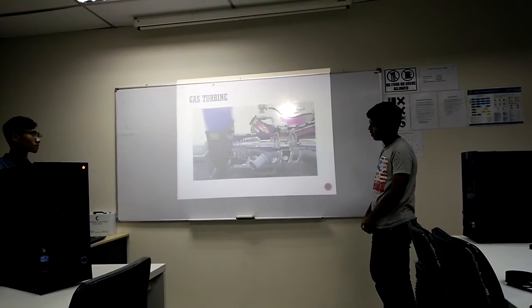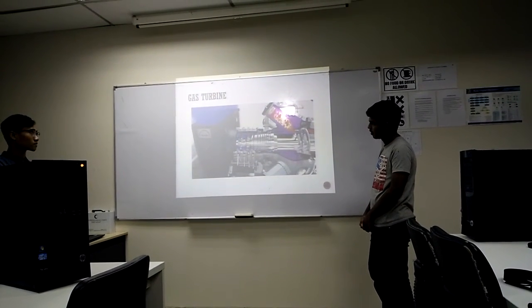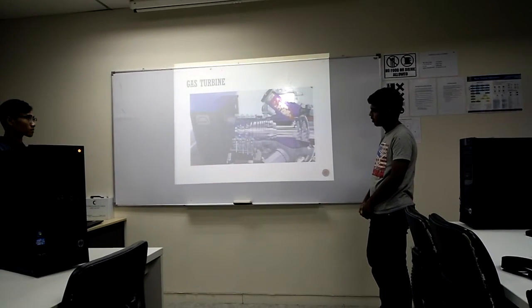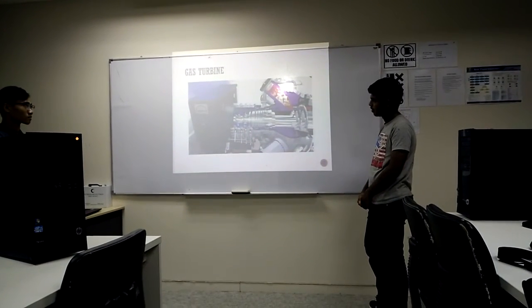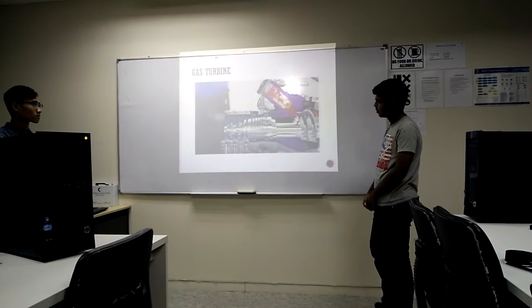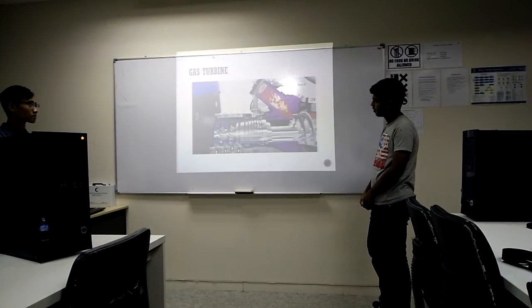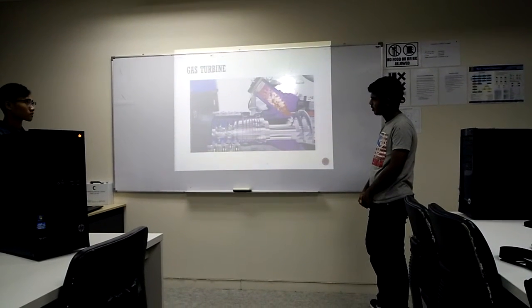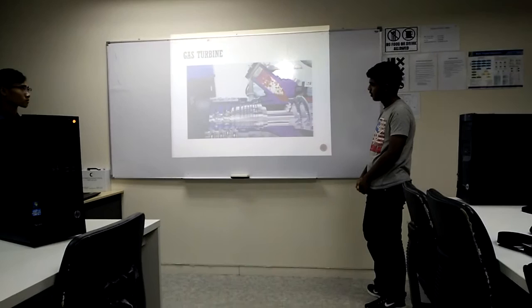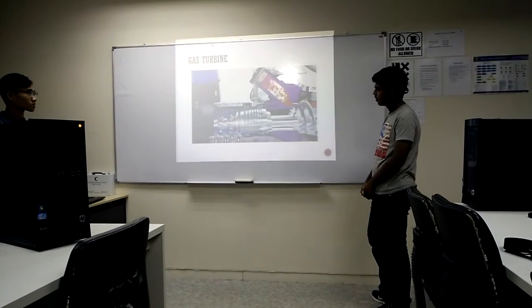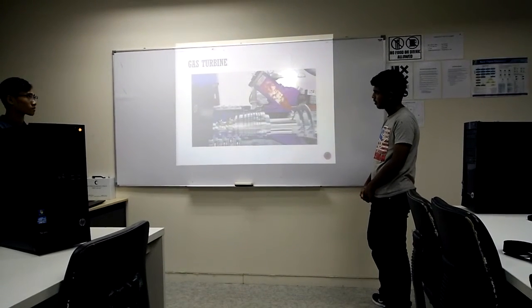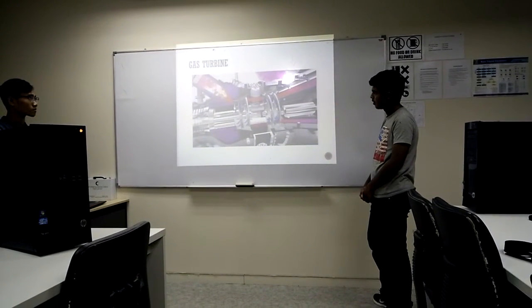Let's take a closer look at this process. Due to the spinning motion, the blades of the axial compressor strike the air. They conduct it into the turbine while compressing it in the process. A flow is created that passes through the air intake casing and then along the axis. A pressure increase of 15 bar means the air flows into the six combustion chambers with around 15 times more oxygen. These advanced CAN combustors premix the fuel gas with the compressed air homogeneously already before it enters the chamber. Afterwards, this mixture is ignited and burns with extremely low emissions.